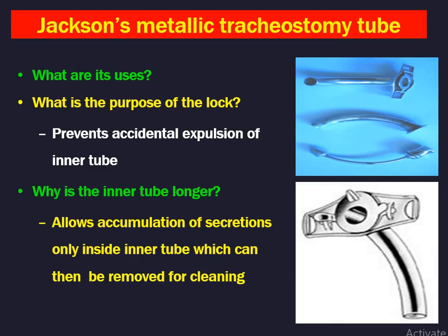Next, tracheostomy tubes. Different types are used but commonly used tubes are metallic and plastic. Metallic tubes can be Jackson's or Fuller's types. The Jackson's metallic tracheostomy tube has an outer tube, inner tube, and obturator. It is used after tracheostomy as the second tube — the first tube is always a cuffed tracheostomy tube because the patient might aspirate secretions. The Jackson's tube does not have a cuff. There is a lock here which prevents accidental expulsion of the inner tube — the inner tube is always kept locked so when the patient coughs the inner tube will not come out.